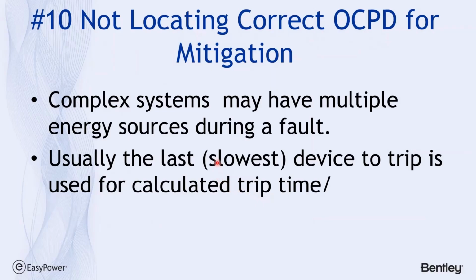Now this last mistake is frequently encountered even by seasoned veterans, and part of it is a lack of ability to look at the insight that the tool provides. Complex systems may have multiple energy sources during a fault. And usually the slowest device to trip is used for calculated trip time. And this is where the integrated method comes into play. And frankly, it works against us.